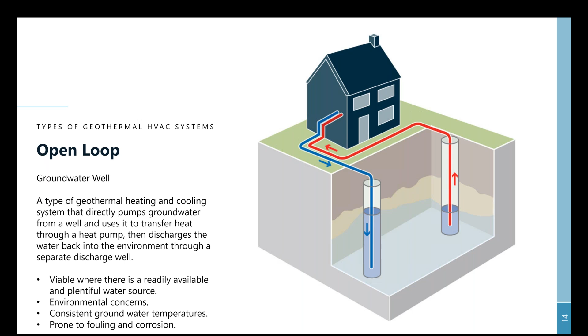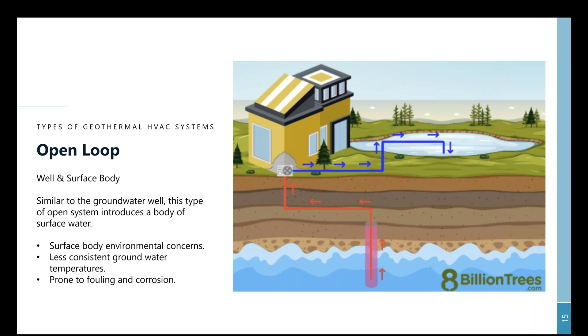Another type of open loop system is what we call a well and surface body system. So it's very similar to the previous example, except in this case, you're trying to utilize some sort of open body of water adjacent to your building to either reject heat into or extract heat out of. Again, you can have environmental concerns with these types of systems as they are sort of open loop. These types of systems tend to have slightly less consistent groundwater temperatures, and really that's based on the fact that you have an open body of water, and depending on the depth of that body of water, it can be very sensitive to ambient conditions. And again, as you are pulling water directly out of the ground or a surface body, these systems can be prone to fouling and corrosion. So filtration and chemical treatment is very important.